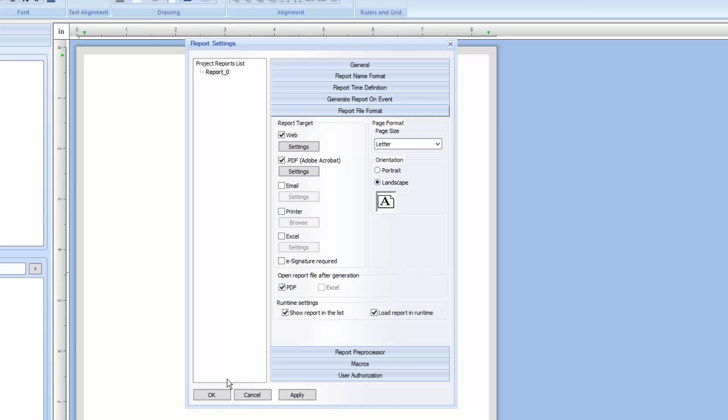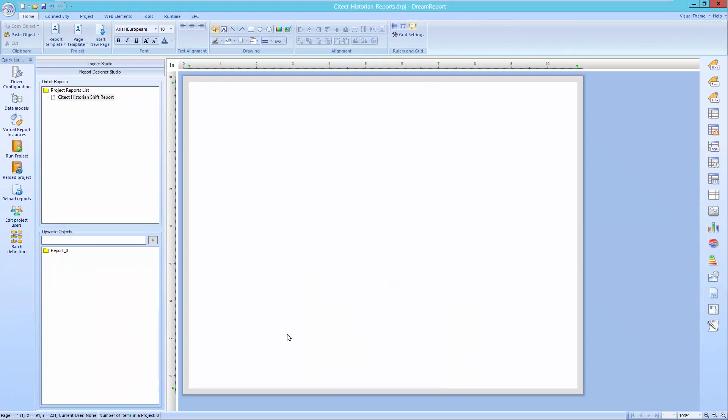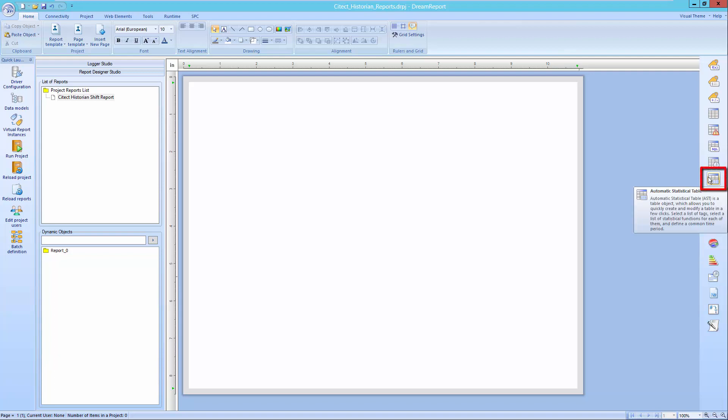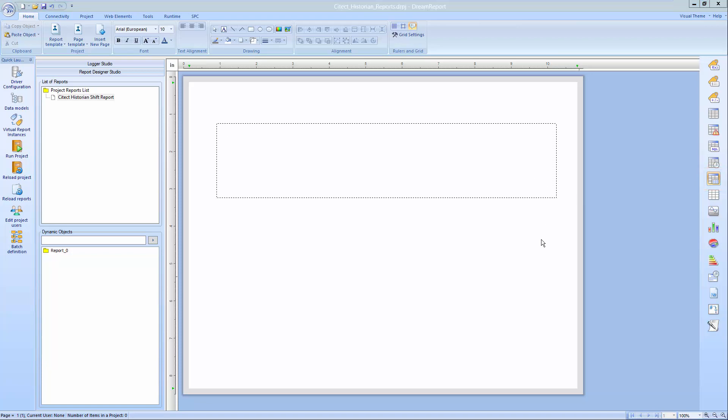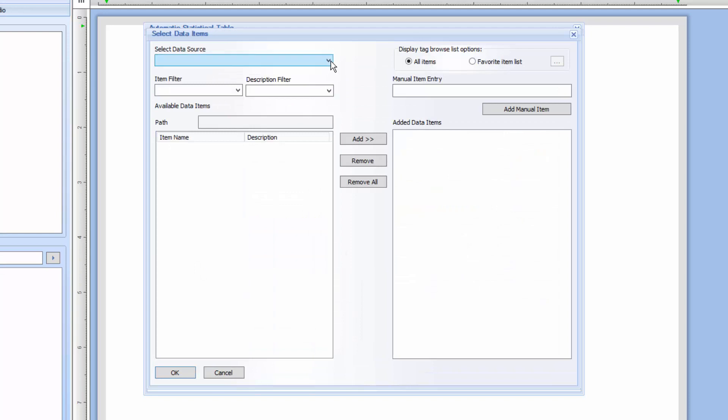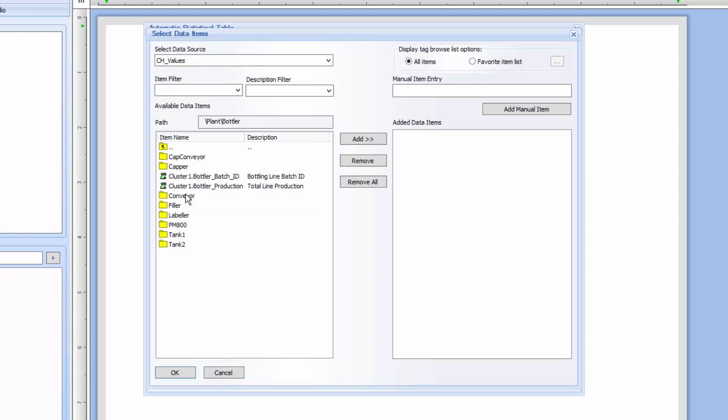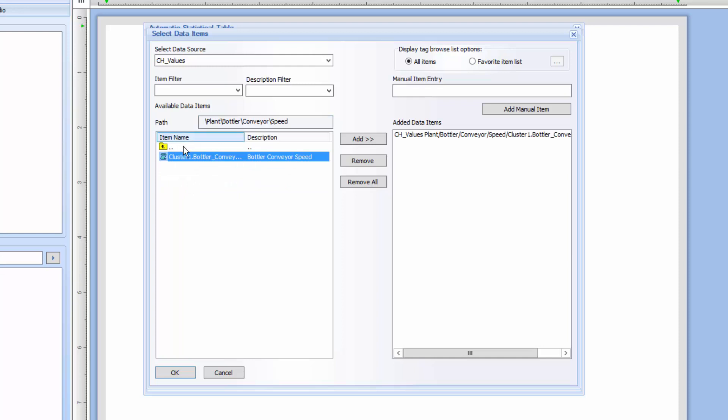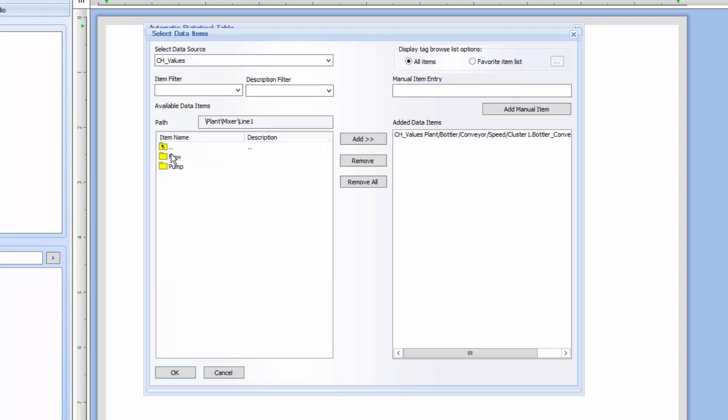Now that we've set the basic report settings, let's start adding objects to the report. I'll be adding a single data object, a table to summarize a set of tags, a line chart, and an alarm table. We'll start with the automatic statistical table to summarize data from a set of analog tags logged in the Citect historian. I'll select the object from the right side toolbar, and then place it on the report. We now need to browse for tags from an external history server. Click the Edit List button, and select the Citect historian data source we created earlier. You'll see that the Citect historian tag folder structure is exposed. I'm going to select a few analog tags from different folders for this table. I'll repeat this until I've selected all my tags.